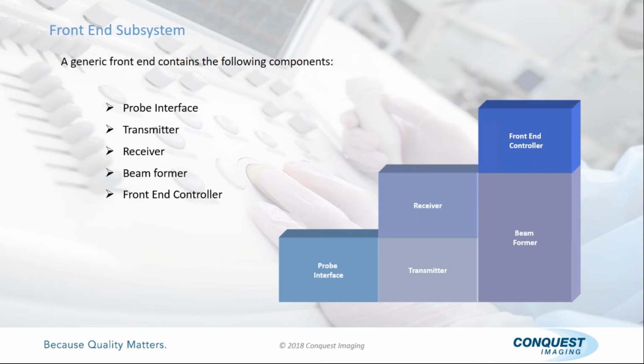Whatever board does front-end control is the only board that talks to the back end. So if the communication between the front end and back end has been interrupted, you only have three things to look at: the back end where the cable plugs in, the cable itself if it is a cable - a lot of them are - and the board it plugs into in the front end.